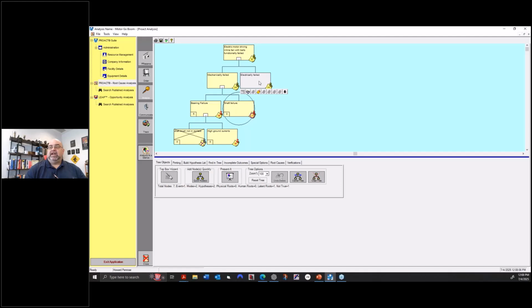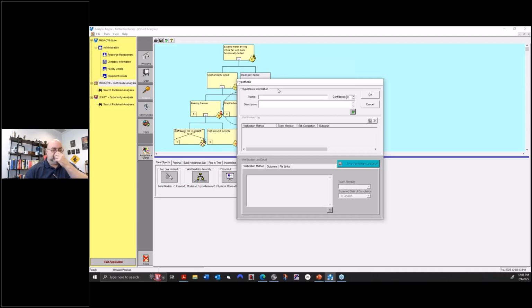So where I end up here is, did it electrically fail? Well, what are the hypotheses? And this is where the data comes in. So I can say, did it electrically fail? Insulation to ground. And I set a confidence level to say, am I confident? So 5 would be, yep, I'm 100% sure. 1 would be, probably not.